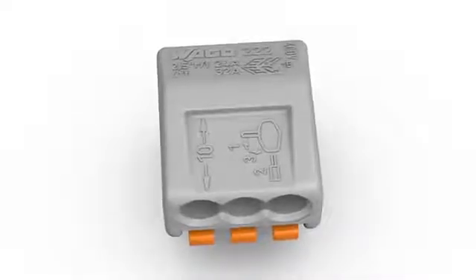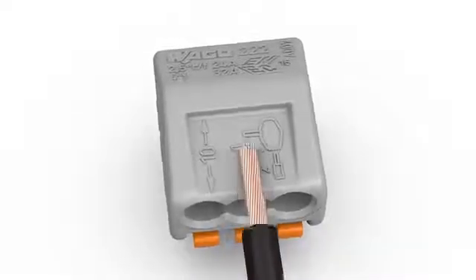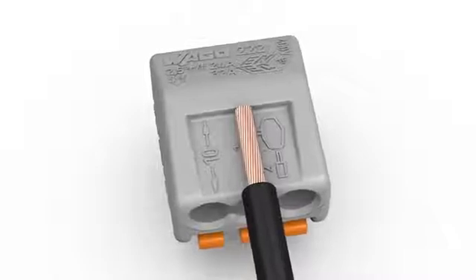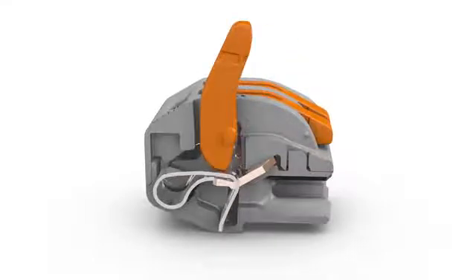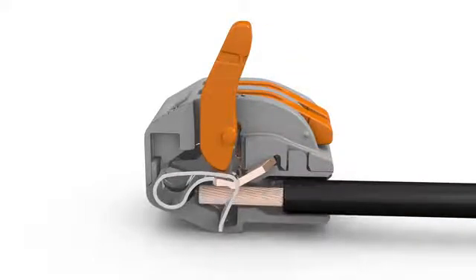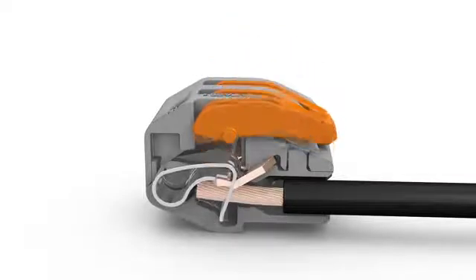Wiring is very easy. Strip conductor to 9 to 10 millimeters or 0.37 inches. Open clamping unit via integrated lever and insert conductor. Then lower lever to close the clamp.